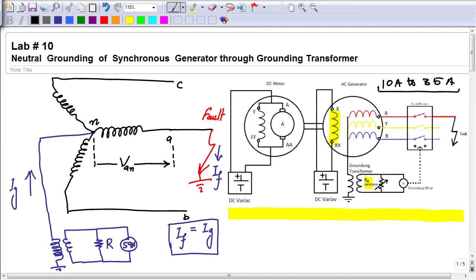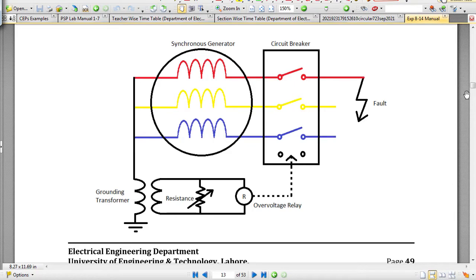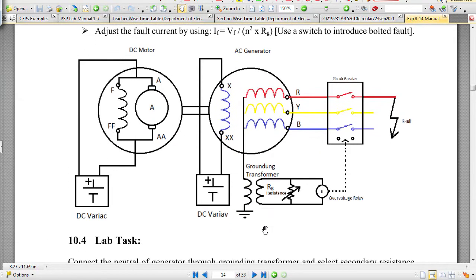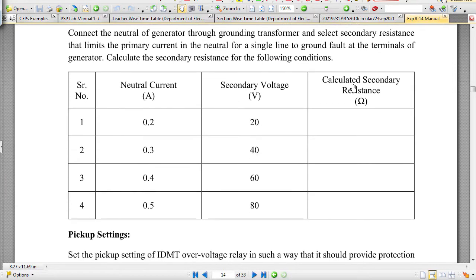Here for the laboratory experiment, the neutral fault current for which we perform the experiment is given in this table. Students will design the value of secondary resistance that will give us a neutral current of 0.2 ampere, 0.3, 0.4 and 0.5 ampere. So these are the voltage ratings of the secondary voltage of that grounding transformer, and the primary is rated at 220 volt. So for different values of secondary side voltage, for fixed primary voltage, students will calculate the value of resistance to be inserted on the secondary side of this grounding transformer to limit the fault current to these values.